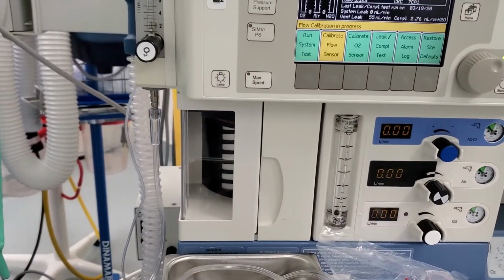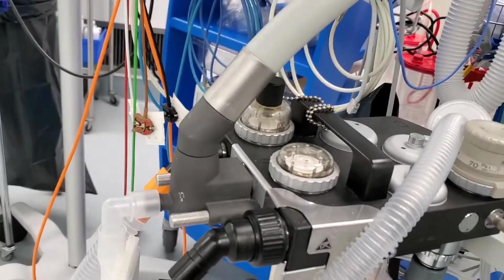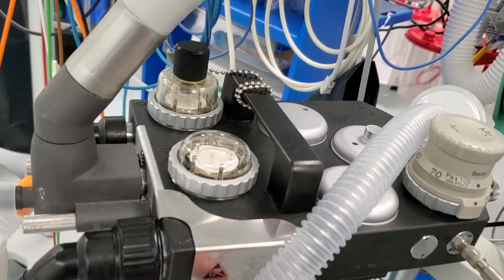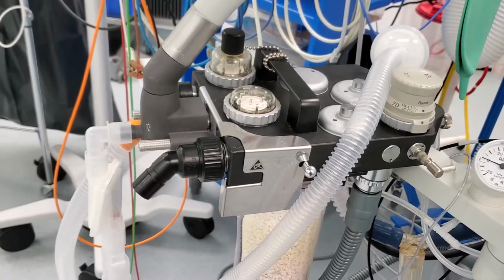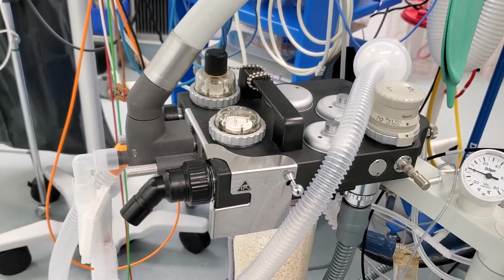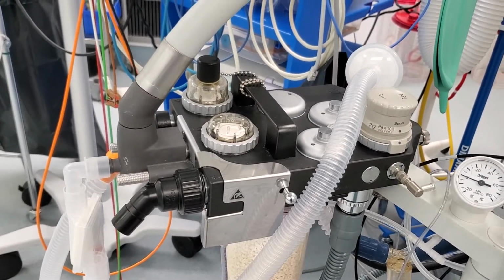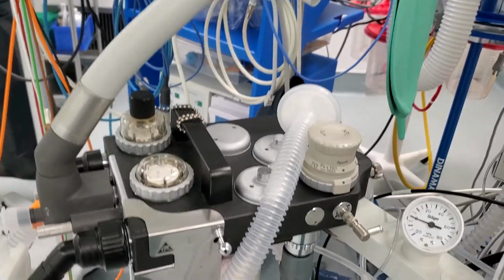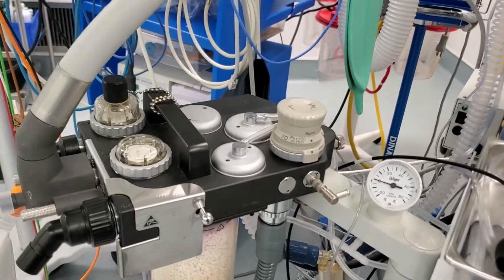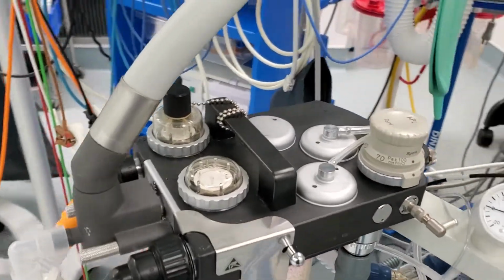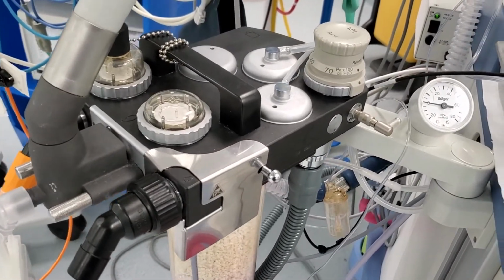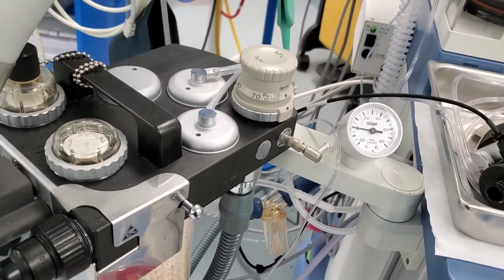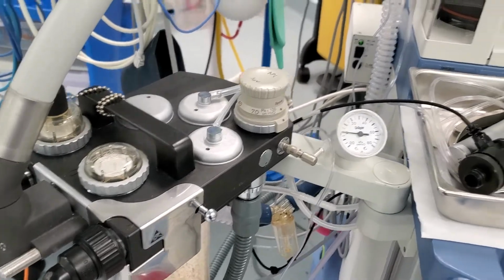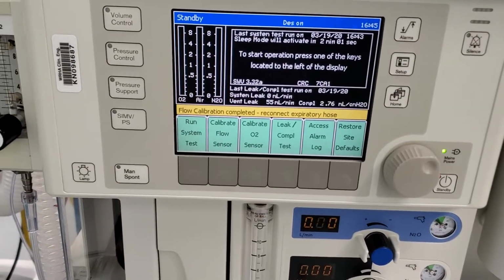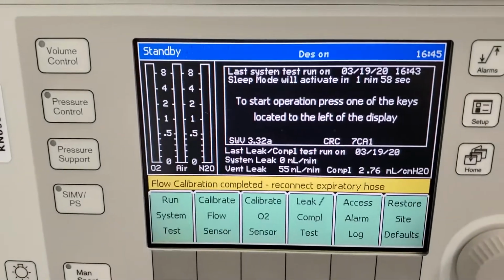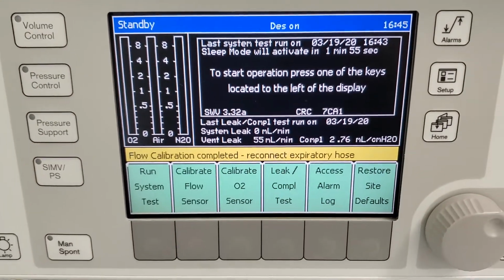Basically what happens, you can see the piston moving up. It's drawing in room air through this port. There is a flow sensor that sits in here. It has 2 heated thermistor wires. When the flow goes by, it causes a temperature drop in the wires, and then that is calculated on a constant. And when your patient is on the ventilator, it will then be able to measure flow coming from the patient. Depending on your frequency set, then that is how your exhaled volumes will be calculated. So it'll prompt you that it has been completed and to reconnect the expiratory hose, which I have already done.